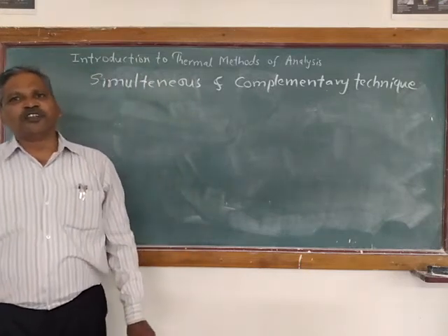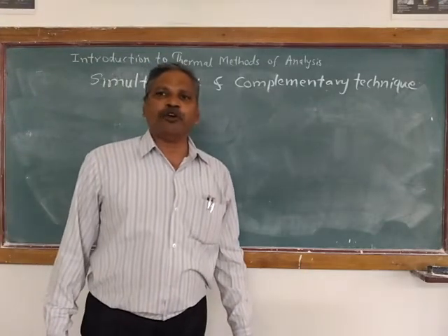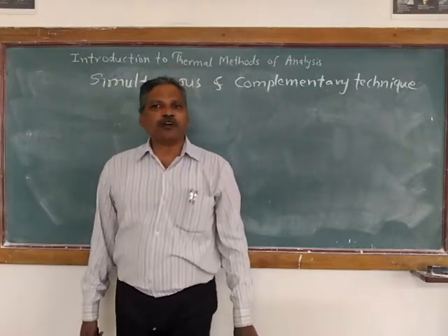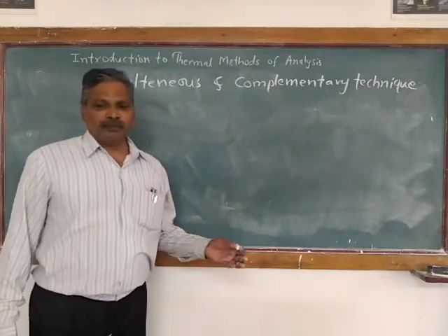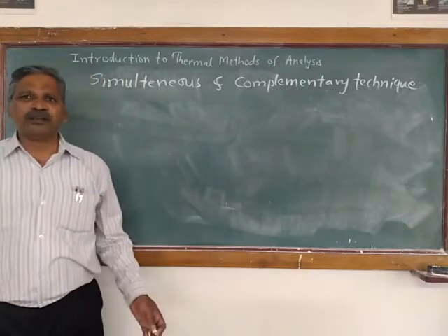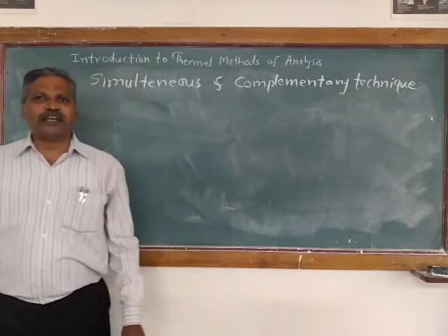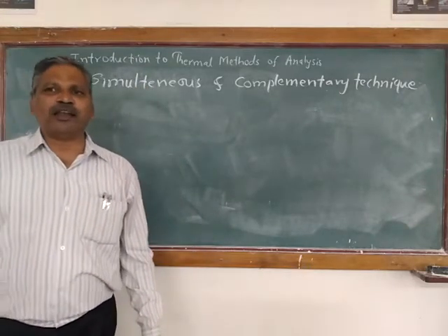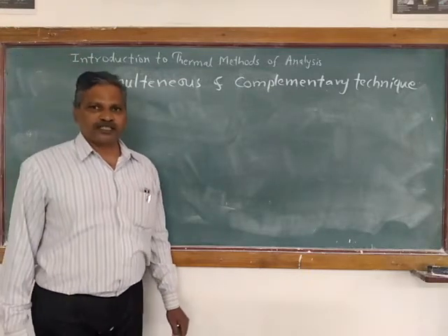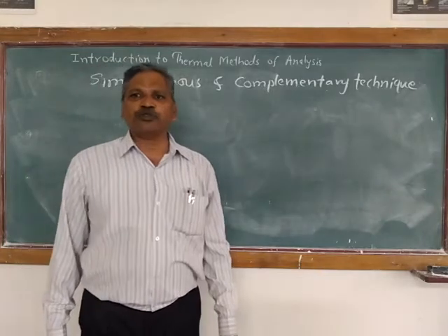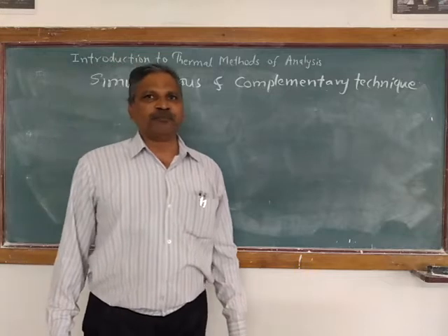Conversely, if the TG curve showed no mass loss, the process of melting could be confirmed by direct observation of the sample. You can see the sample directly, whether it is melting or not. So the melting of the sample is confirmed by direct observation of the sample. It is clear that combining several analytical methods gives a better profile of the changes taking place, although we may have to sacrifice the optimum conditions for each separate technique.